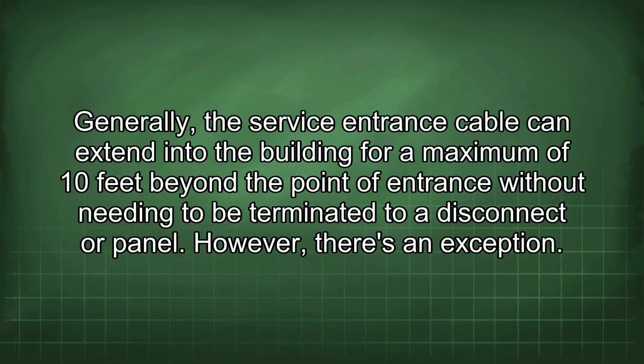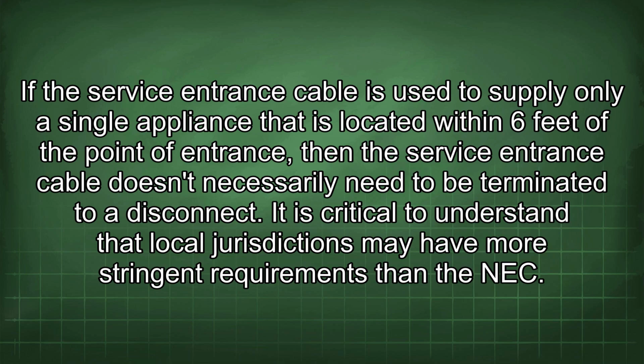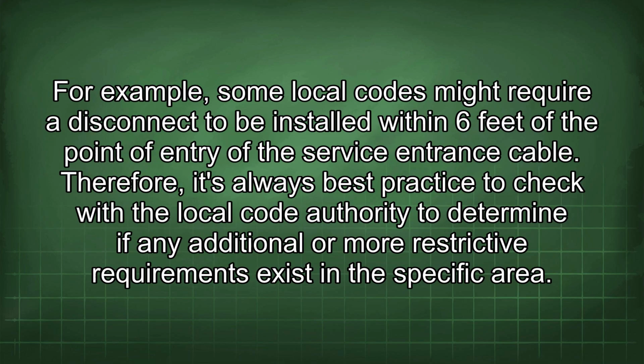However, there's an exception. If the service entrance cable is used to supply only a single appliance that is located within 6 feet of the point of entrance, then the service entrance cable doesn't necessarily need to be terminated to a disconnect. It is critical to understand that local jurisdictions may have more stringent requirements than the NEC. For example, some local codes might require a disconnect to be installed within 6 feet of the point of entry of the service entrance cable. Therefore, it's always best practice to check with a local code authority to determine if any additional or more restrictive requirements exist in the specific area.